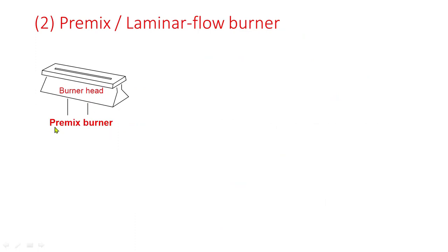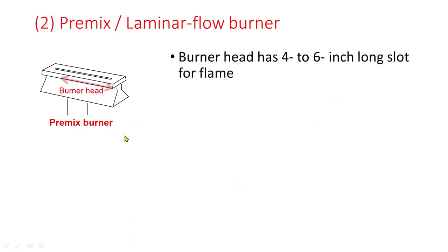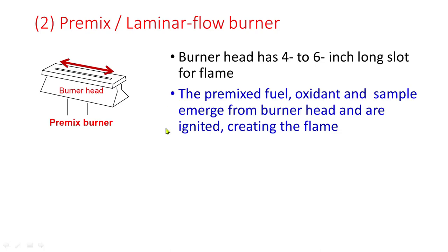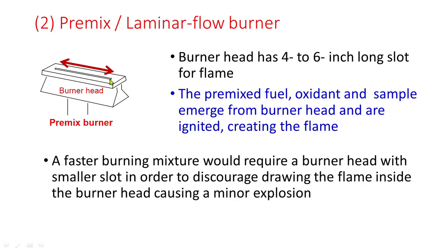This is the burner head of the premix burner. The burner head has a 4- to 6-inch long slot for the flame. The premixed fuel, oxidant, and sample emerge from the burner head and are ignited, creating the flame. A faster-burning mixture requires a burner head with a smaller slot to discourage drawing the flame inside the burner head, causing a minor explosion.